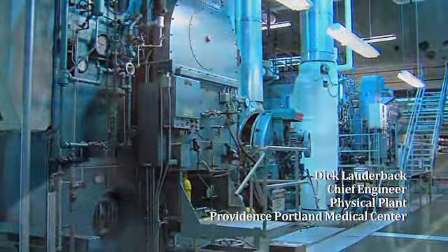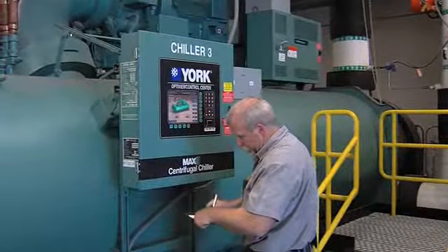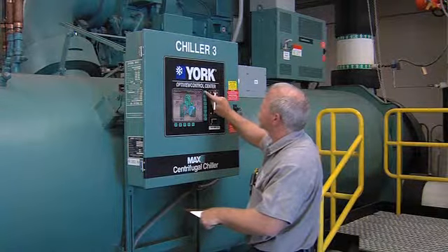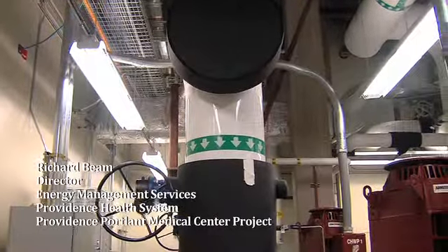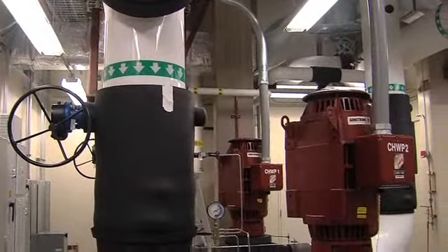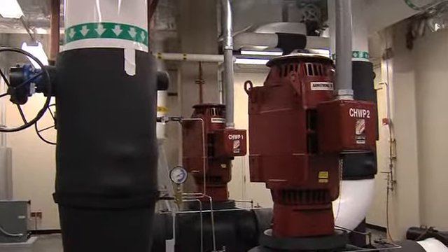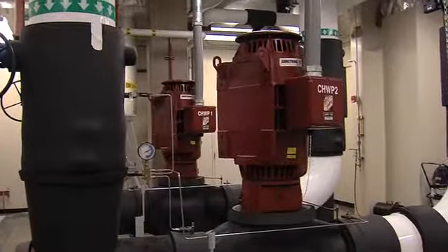We've moved this up. We've got 3 1,200-ton chillers here now. We've incorporated energy savings in heat exchangers and plate exchangers. Everything about the chilled water system has variability built into it. The chillers themselves and the pumps are on variable speed drives. If set up properly, you aren't just running a motor at 100%.